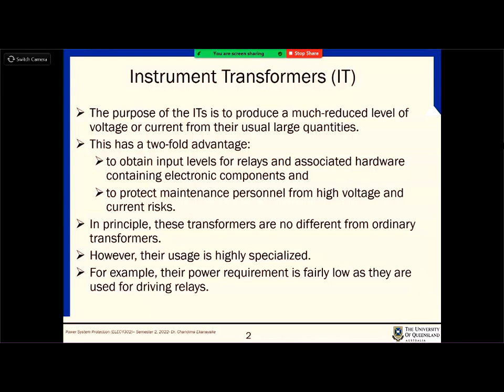From the operation point of view, they are no different from normal transformers. If you know the purpose of a transformer, then that is the same thing here. It can drop the voltages or it can drop the current magnitudes. That's what it does. Among recent developments, there are things without this transform operation, like Hall effect sensors. You can use them as CTs. There are ways to get the information without using instrument transformers. Probably in decades' time, these things will not be used. You can use Hall effect sensors to measure current and voltage, but they are not as reliable as them still. But with time things change, right?